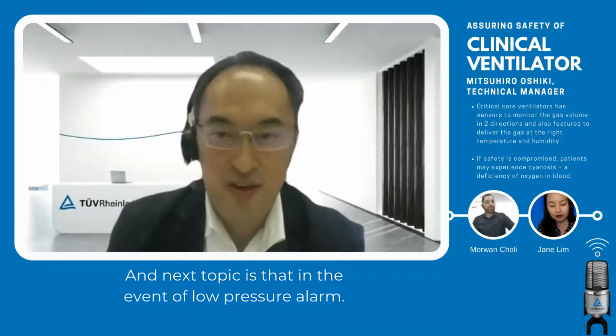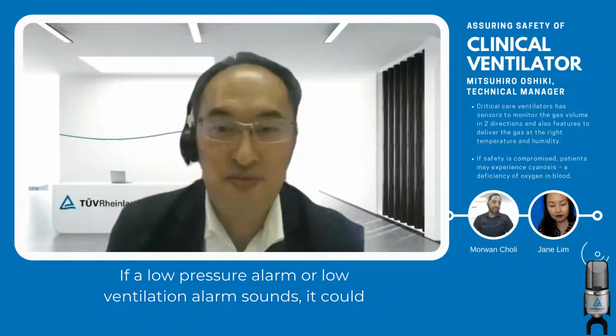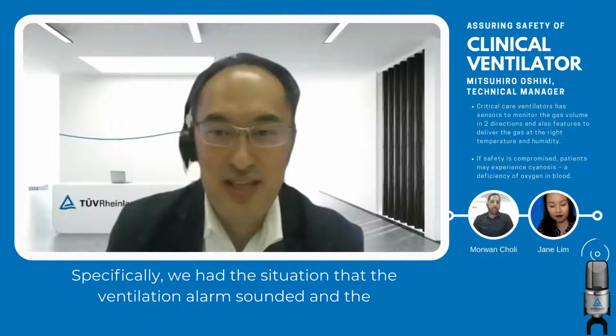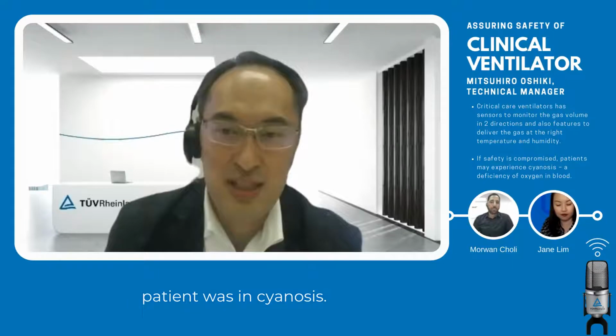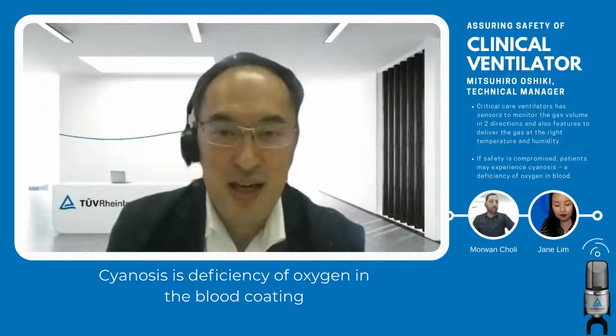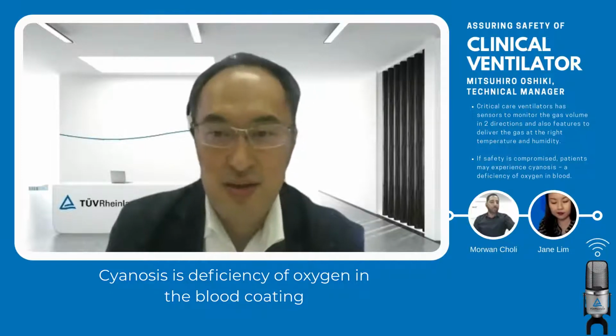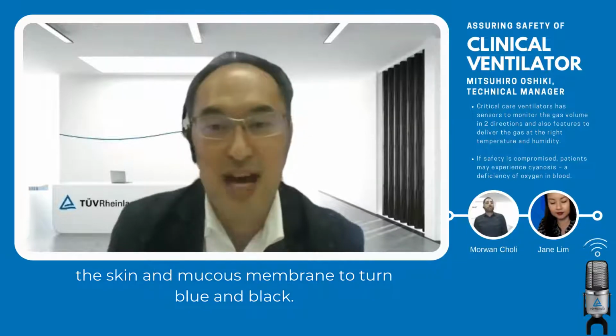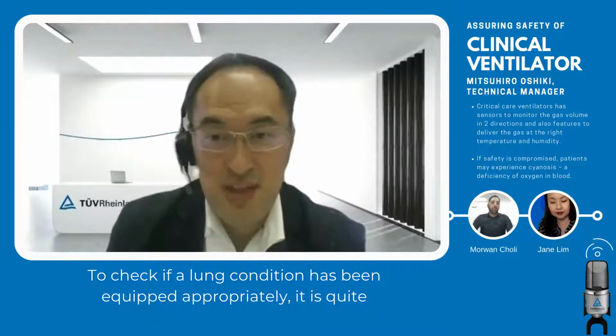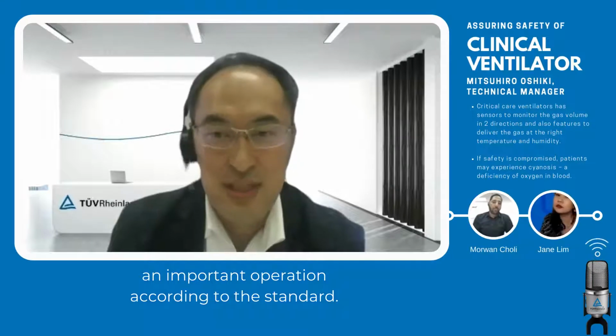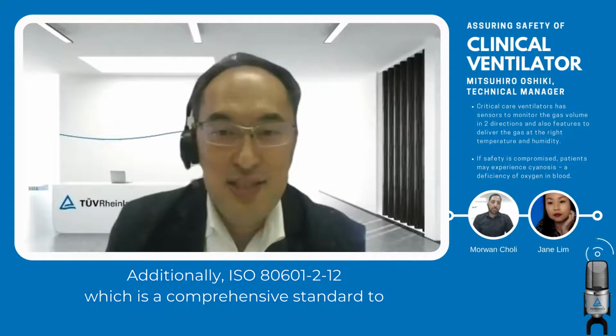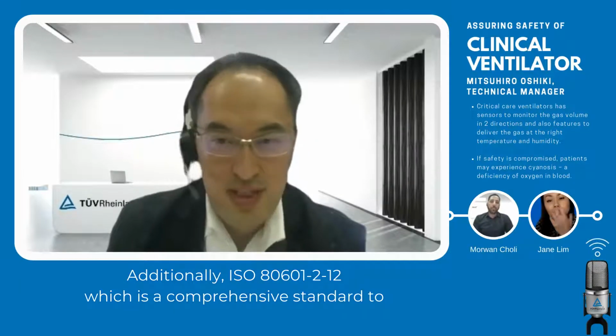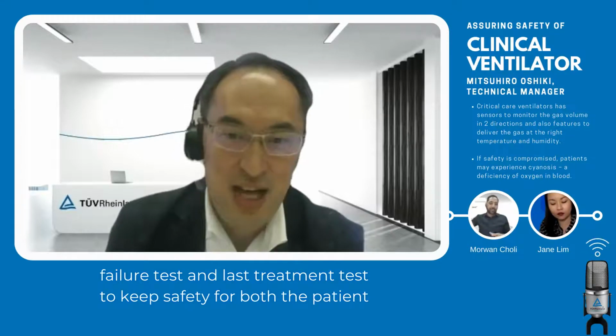And the next topic is the event of a low pressure alarm. If a low pressure alarm or low ventilation alarm sounds, it could be a gas leak from the circuit. Specifically, we had a situation where the ventilation alarm sounded and the patient was in cyanosis. Cyanosis is a deficiency of oxygen in the blood, causing the skin and mucous membrane to turn blue and black. To check if the alarm condition has been equipped appropriately is quite an important evaluation according to the standard. And additionally, ISO 80601-2-12, which is a comprehensive standard to conform to current ventilation technologies, includes electrical failure tests and rough treatment tests to keep safety for both the patient and the operator.